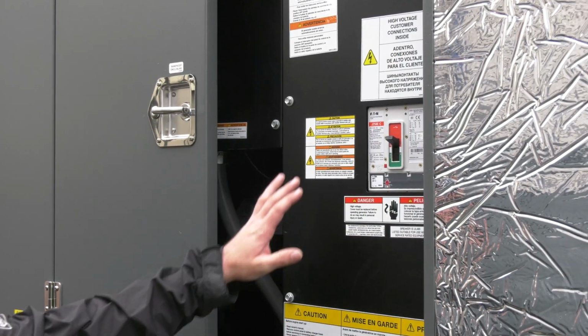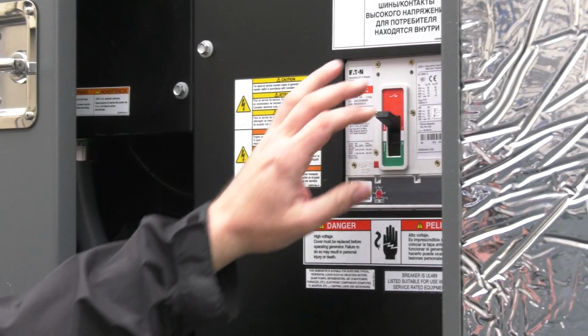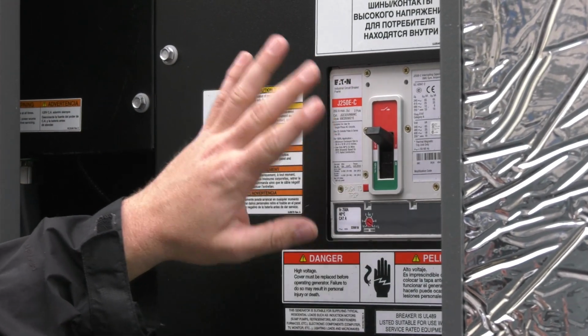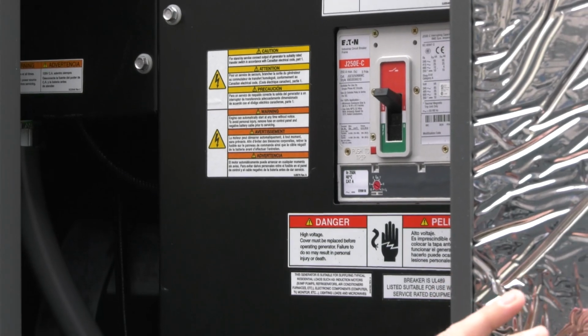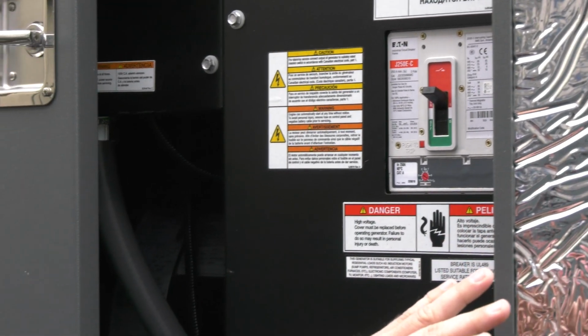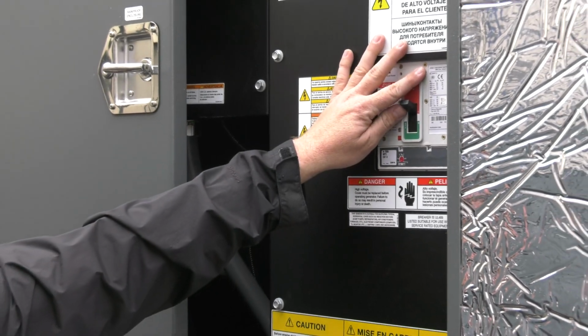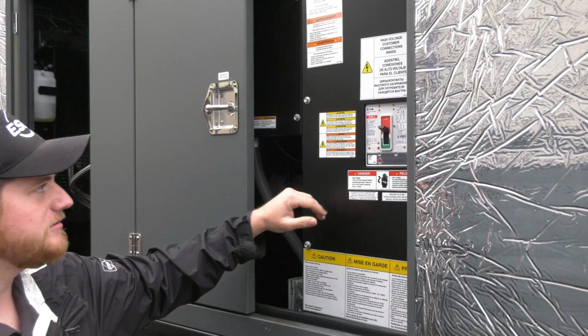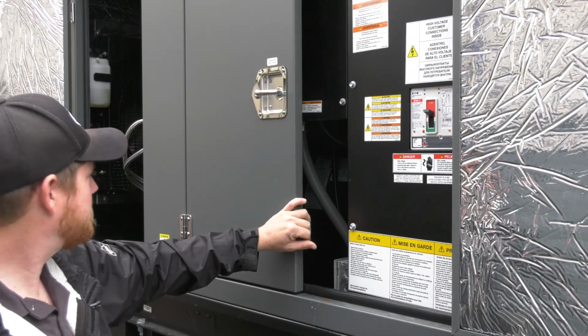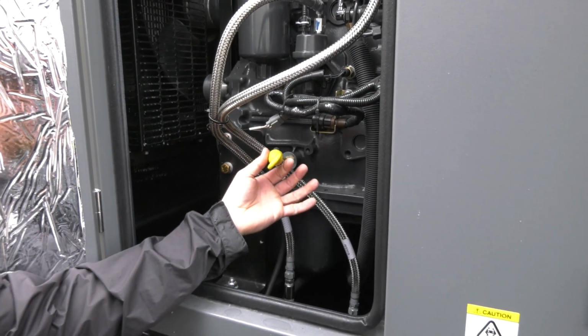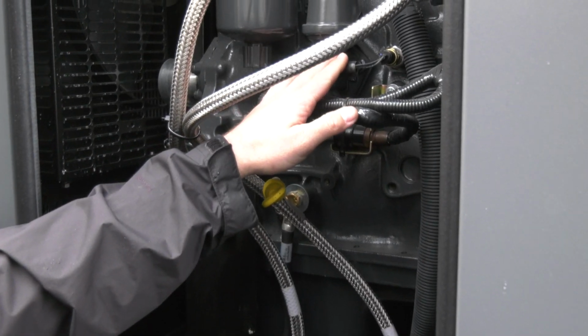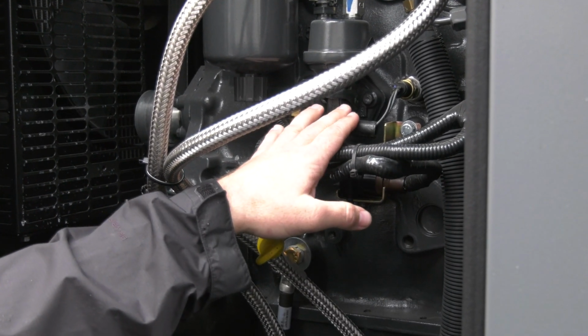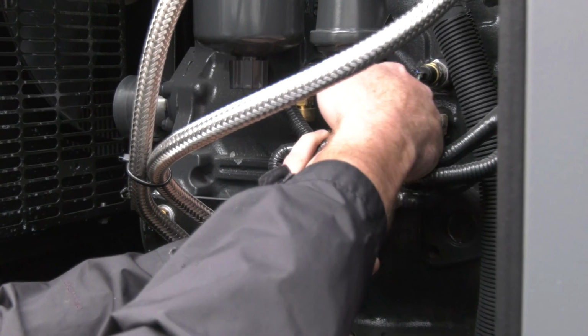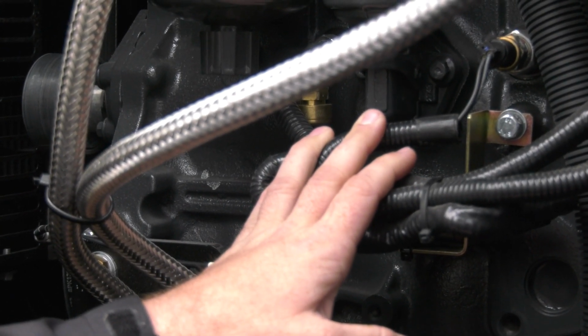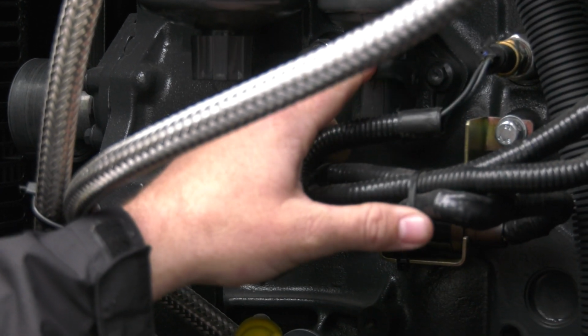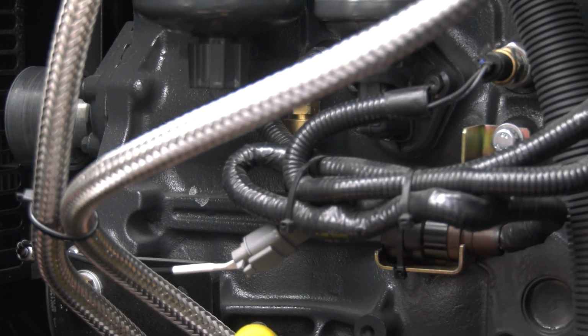All right, this unit has 2 breakers. The main is here. There's another one on the other side that's identical to this one. So if you ever have an auxiliary 2 or a source 2 fault at the switch, and this is running, check breakers first, obviously, make sure you don't have an open breaker. Other than that, and this basic engine stuff, here's your oil dipstick if you need to check the oil. If you ever run into a situation where it's in an overcrank scenario, this is your fuel pump, lift pump primer. So if it's an overcrank not wanting to start, you can start there, trying to reprime the system and get it going.